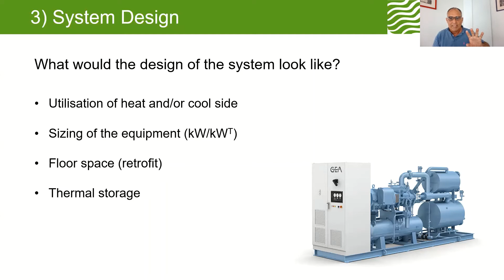I just have to explain this bit briefly. If we're talking about the inlet temperature of the heat pump, with a target temperature of say 50 degrees, heat at 12 degrees on the low, cool side of the heat pump can be valuable to you. Coming from the gas side, we're looking for an output of say 50 or 70 degrees, and you're not really fussed about the temperature of the water coming into the gas system, but you are with a heat pump.